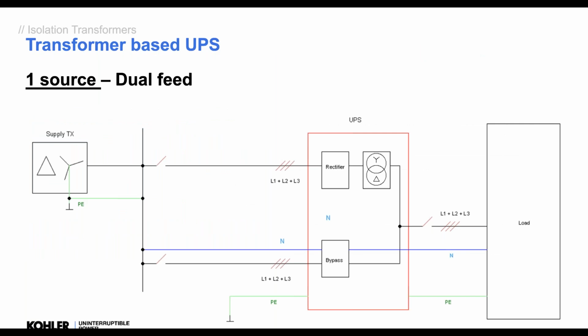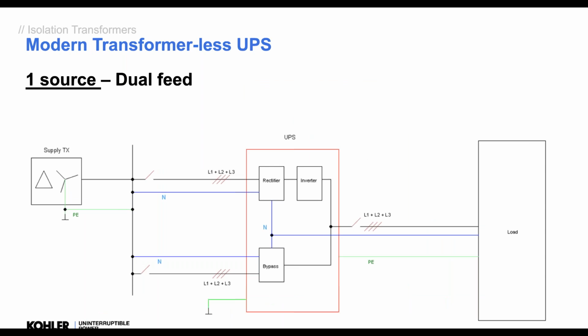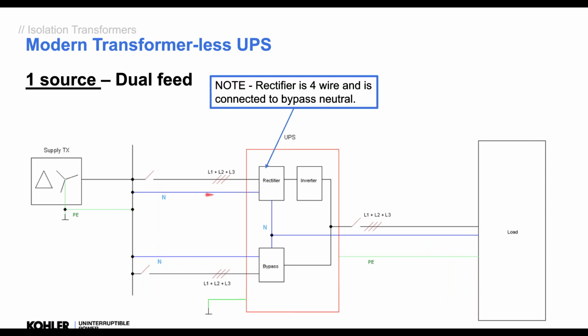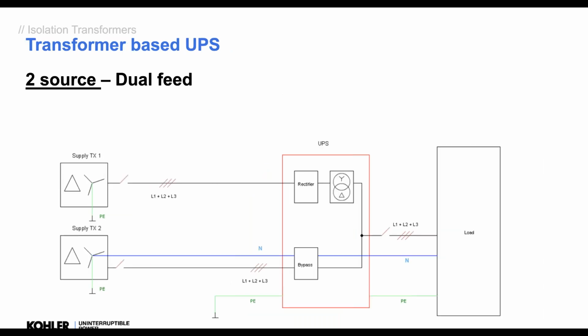So what we're saying is that an old transformer-based UPS would only have a three-wire rectifier. The bypass would have the neutral, and that went all the way through the UPS, not connected anywhere else, out to the load. Okay, so that's no problem. With a modern UPS, we have a four-wire rectifier and a four-wire bypass, and that neutral is linked inside. Okay, so if we have different supplies, we will link that neutral, and that is an issue.